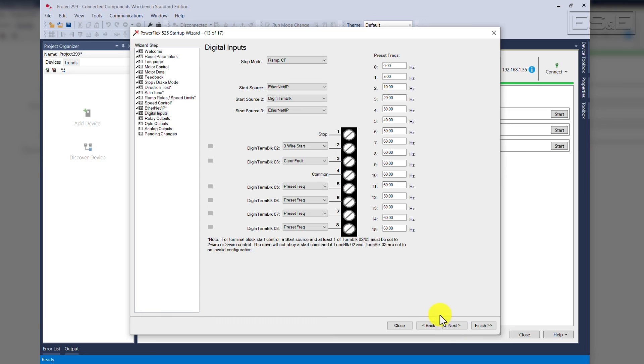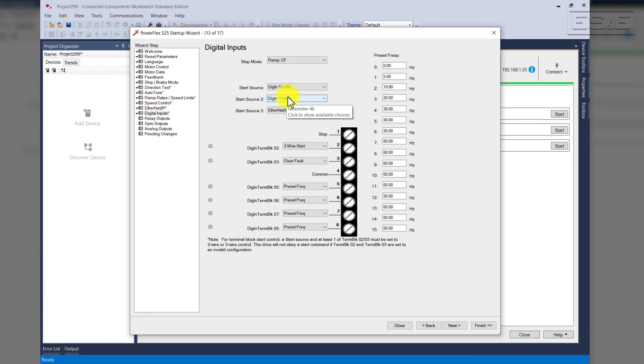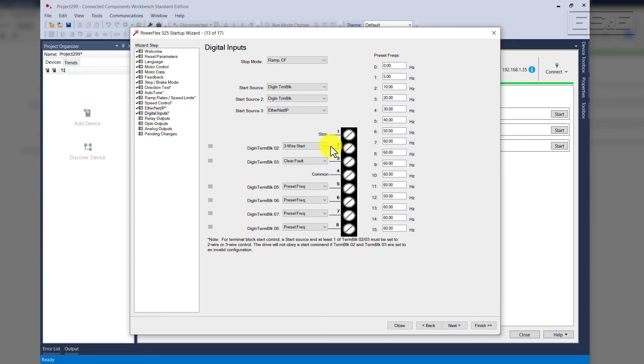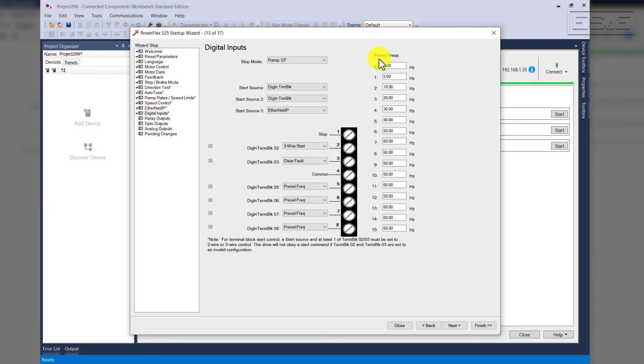Digital inputs. Our stop mode was ramp clear faults. Our start source, we're going to use digital inputs. At this point, we're going to use digital input number two. I've set it for three-wire start. Digital input three, we're going to use it for the clear faults, but there's many options for the digital inputs. Also, here you'll see preset. These are preset frequencies if you choose to use those, and they can be edited at this point. Click Next.